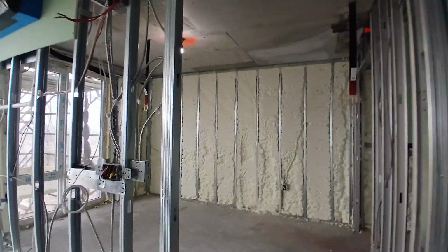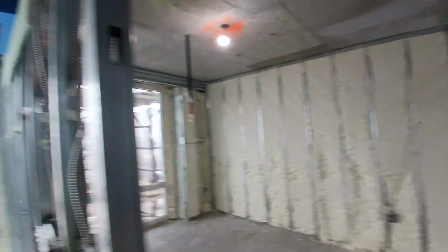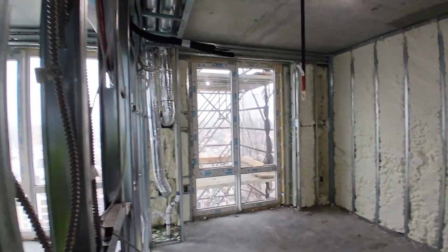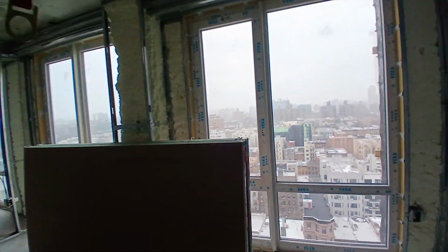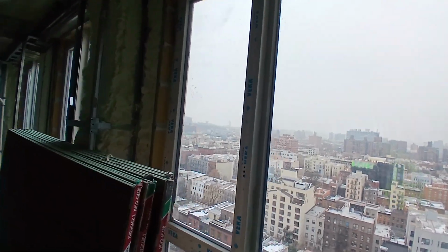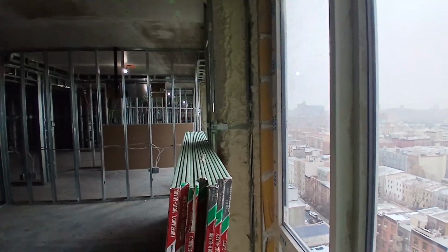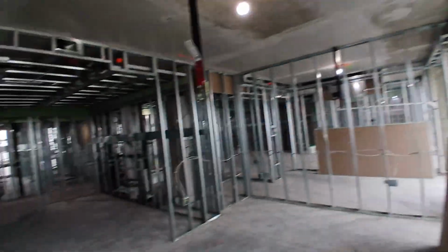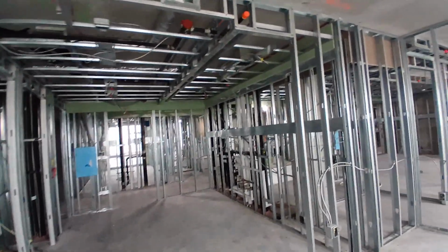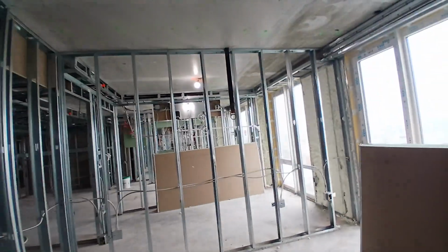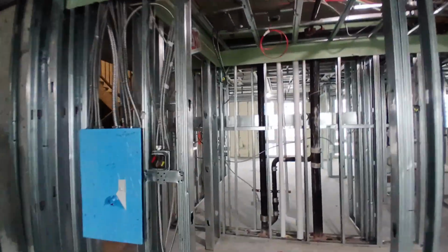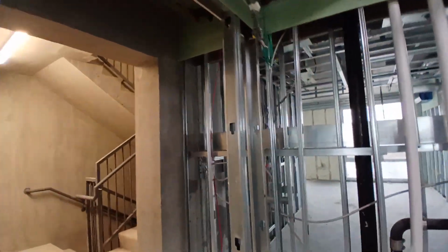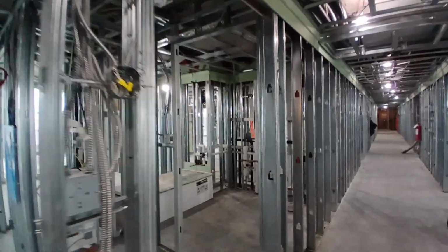You can see 6 inches of applied foam insulation on the walls. 24R approximately. Every inch of open cell foam insulation provides an R value per inch of 3.9 to 4.1, depending on the material, right? We don't have the certificate, so I don't know what is the specific R value per inch for this open cell foam insulation.